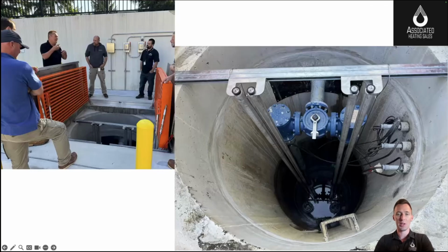This is State of Michigan, Hall of Justice. They have a truck dock in the back where they drain a lot of groundwater because it's below grade from the surrounding areas. This is an example of where this valve assembly was really valuable to the maintenance staff. What we did is, these are 15 horsepower, I believe, 6-inch pumps. And the 6-inch valve assembly went in really nicely and saved us from having a valve box next door. I mean, this is all existing and this is sort of a retrofit. So this worked really well for that. And it's right near the top. When we went out to do the startup, the maintenance personnel was describing how awful the old system was to work on. You had the valves and everything down below within the pit. So this represented a big upgrade for them.